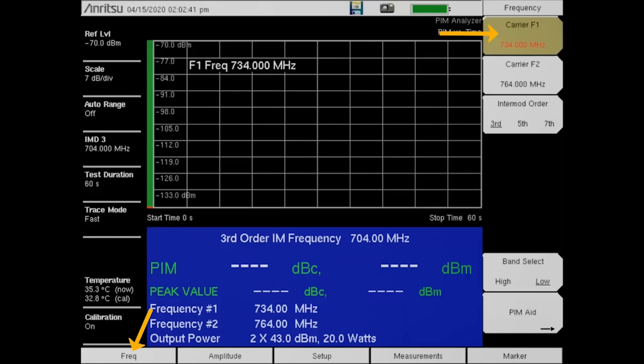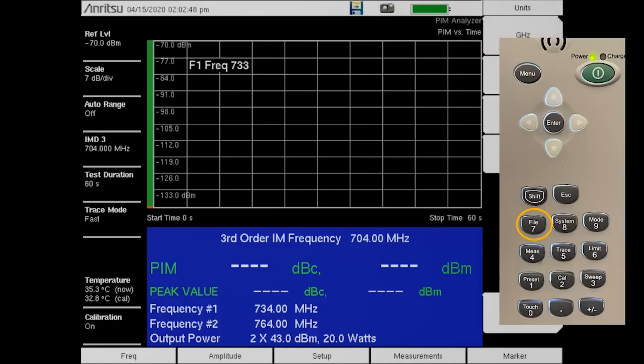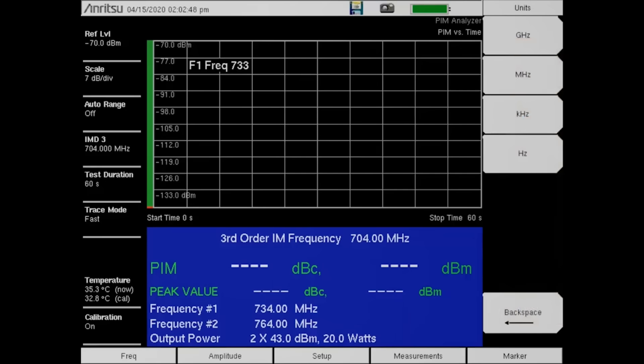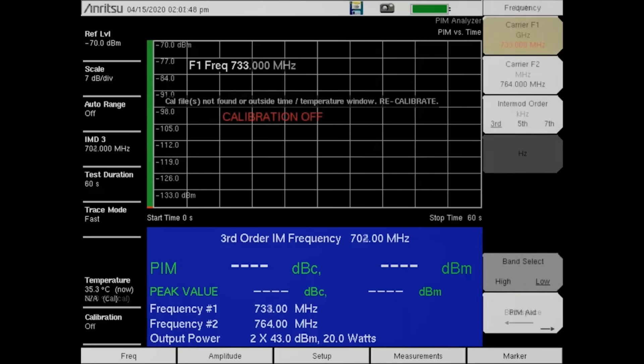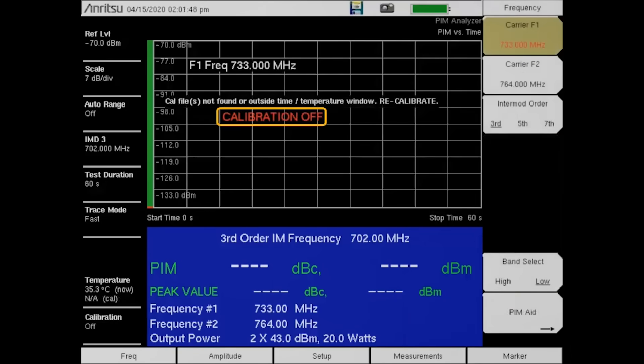From the keypad, enter 733 and then press the megahertz key. With the custom transmit frequencies entered, we can recalibrate. Take notice of the calibration off indicator on the screen.